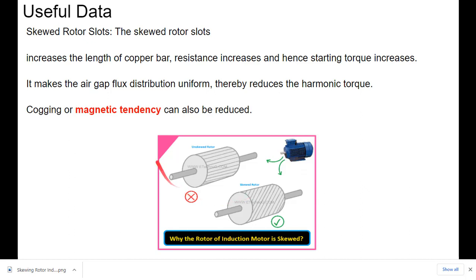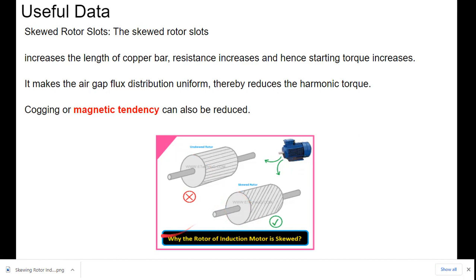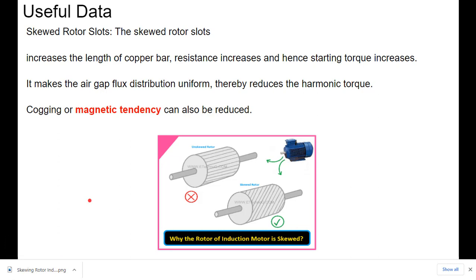Also, it makes the air gap flux distribution uniform thereby reduces the harmonic torque. Also, magnetic locking or magnetic tendency can also be reduced. So in induction motors, skewing the rotor bars through some angle prevents magnetic locking or magnetic tendency, makes the air gap flux uniform, and increases the starting torque.